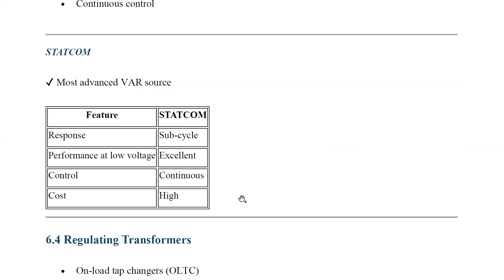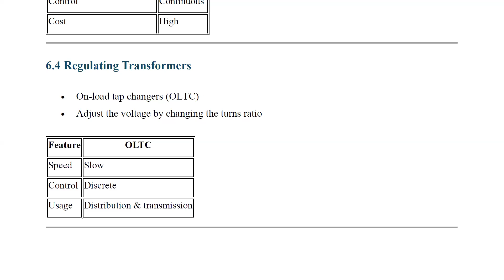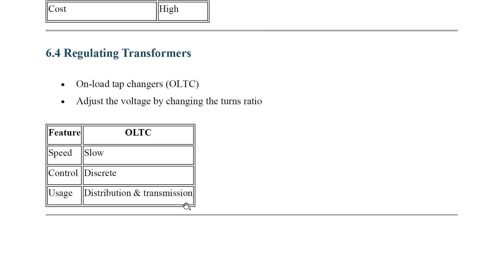Next, regulating transformers, like on-load tap changing transformers, are also there. With a sudden change in the load, the transformer will react automatically. Tap changing transformers increase or decrease voltages, depending on the winding. If a sudden rise in the voltage happens, you need to change the winding, so the voltage gets adjusted. It adjusts the voltage by changing the turns ratio of the transformer. As a feature, OLTCs, on-load tap changing transformers, are slow and the control is discrete. Usage is in distribution and transmission. We are using these OLTC transformers.